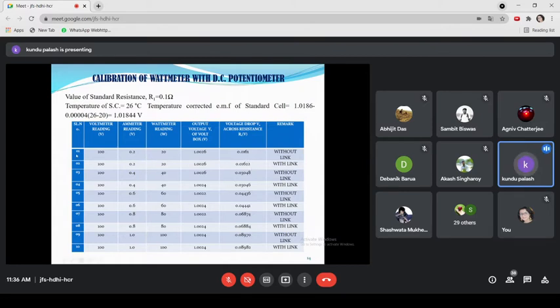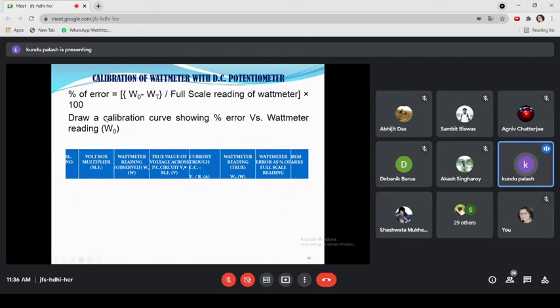So for each setting, keeping the voltage constant and varying the current, you will get 2 readings. For 20% of the full scale current, there will be 2 readings; for 40% of the full scale current, 2 readings; likewise at 100%, the rated value of the full scale current, there will also be 2 readings. So these are the nature of the readings. You have to draw the calibration curve in your report showing percentage error versus wattmeter reading W0. So the y-axis will be the percentage error according to the formula, and the x-axis is the wattmeter reading, the test wattmeter reading W0.